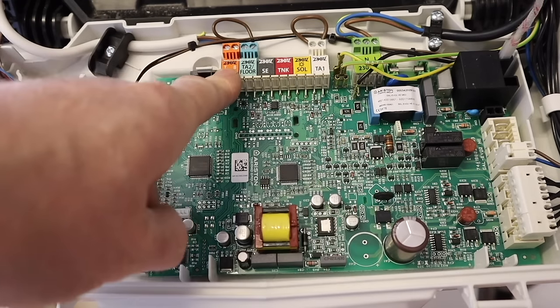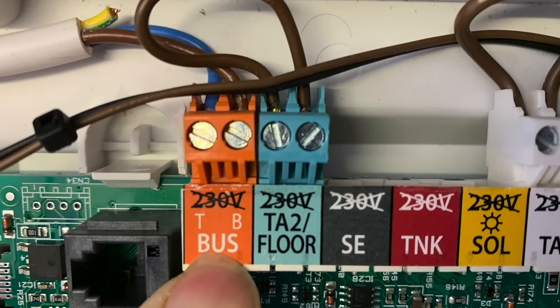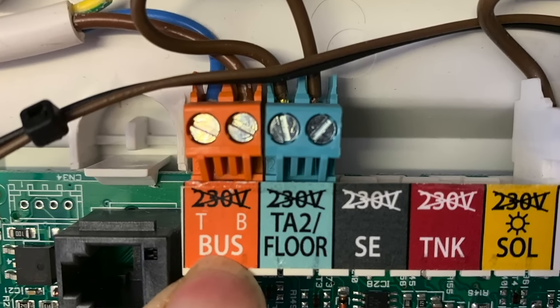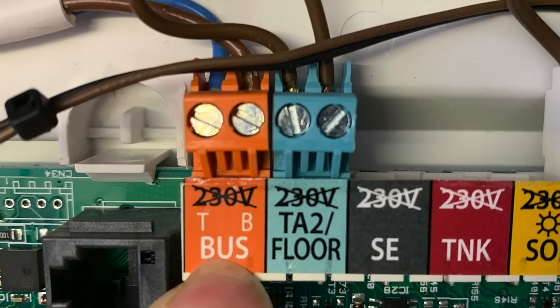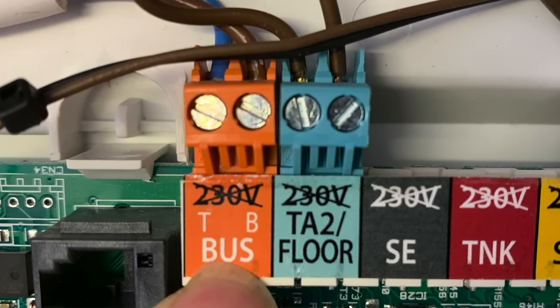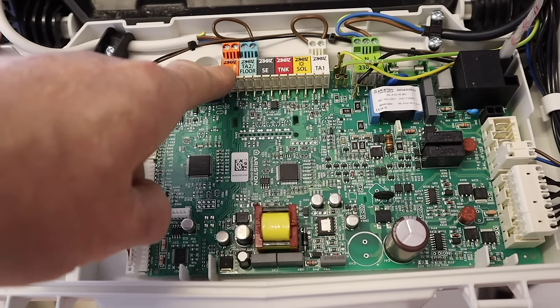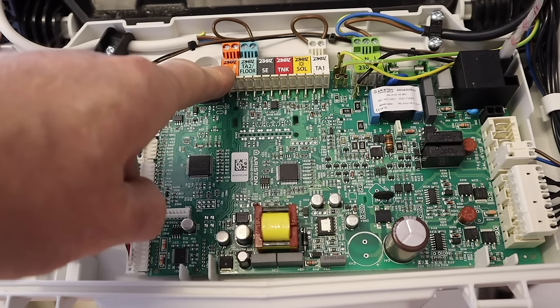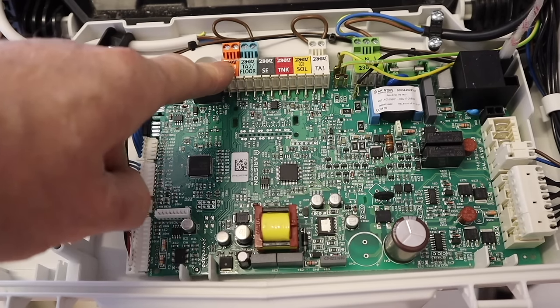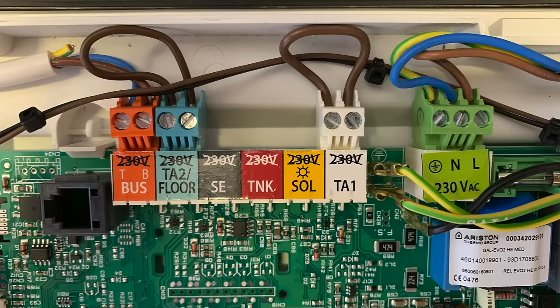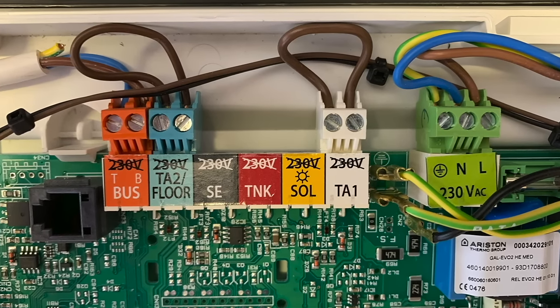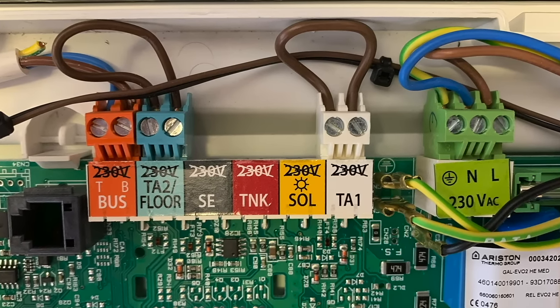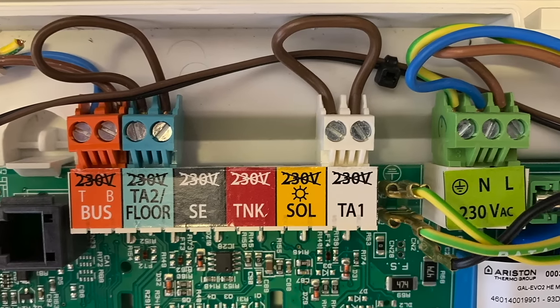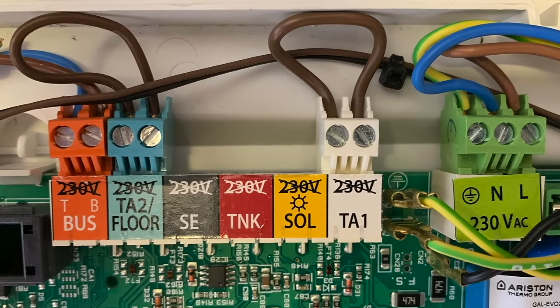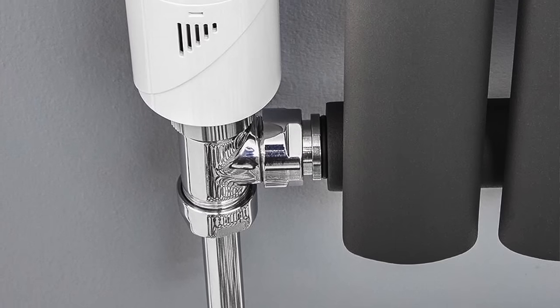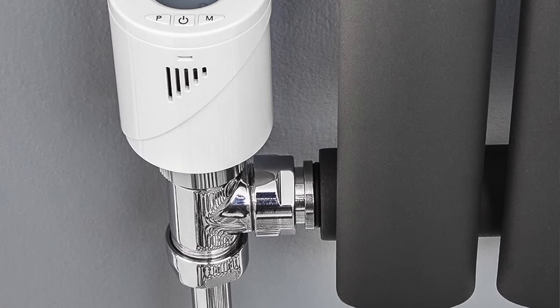This orange one is their bus connection, and this is their OpenTherm bus connection. So this is where they would connect on it. Typically, using OpenTherm can provide you with around 6% energy savings on top of anything that the smart thermostat can do anyway. Exact figures will depend upon the home, the number of radiators, the heating temperature, and whether or not individual smart radiator valves have been installed on the system.